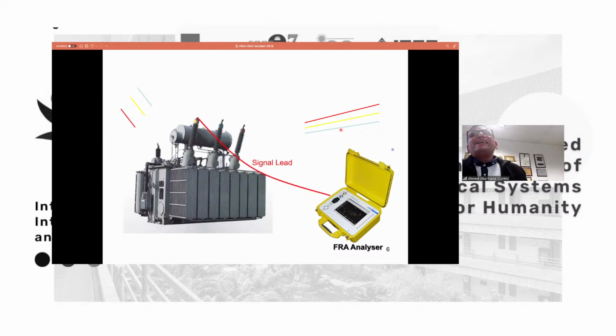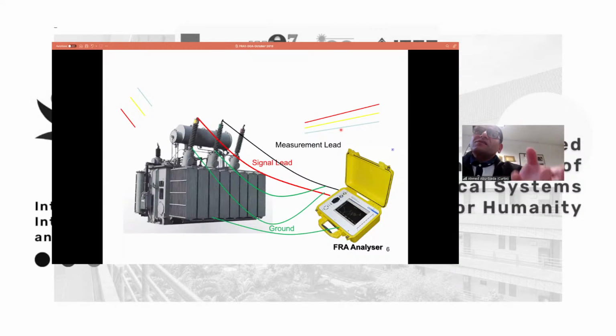And then you scan each phase of the transformer, phase A, phase B, phase C, with this small device. The device is called a frequency response analyzer, which injects a very low voltage, 10 volts only. But the voltage here is of variable frequency from 10 hertz to 2 megahertz. And you measure the impedance or admittance or the transfer function of each phase against the frequency. That's called the frequency spectrum or characteristic of each phase.